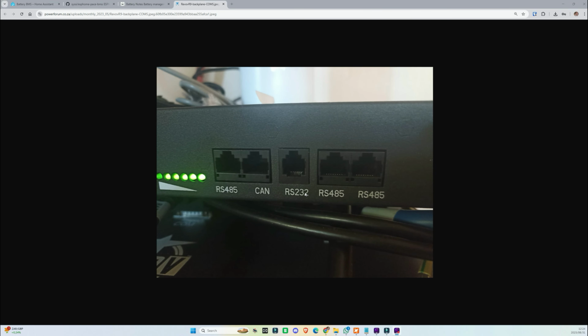On the BSLs, it's not that these ports are disabled, they're usually used for communications with your inverter. On SunSyncs and Deyes, you're using the CAN bus port, and the default is pylon emulation on both the CAN bus and RS485 port. So they're both set to pylon as standard, and you need to get that changed to Modbus so you can query it with Modbus queries. That's just how these are set up, and it was one of the reasons I could never get my connection to work - it's not set for Modbus as standard, and you need to change that using PBMS tools, or ask the guys at BSL Get Off Grid to help. They're very helpful, and once I figured out that was the problem, it was easy to sort out.